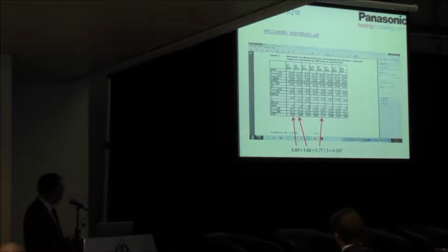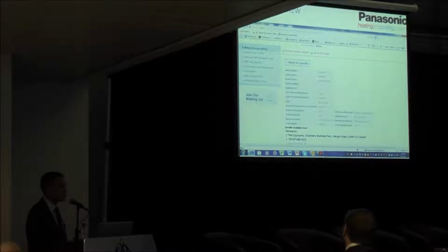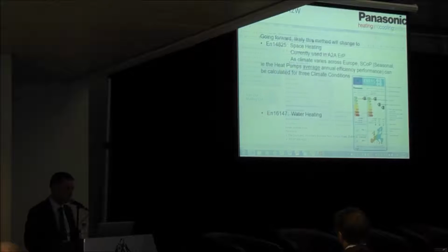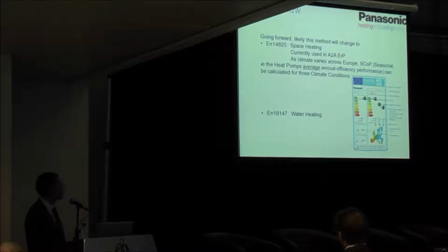But when we look at the three conditions that we have to test it to for HARP, which are air at 7, water at 35, air at 2, water at 35, and air at 7, water at 45, we get an average figure of 4.107. So that's the figure that the BER assessor then uses, and that's what he sees on the HARP database. It gives the information about the unit, when it was manufactured, the SPF, the seasonal performance factor, and then contact details for the manufacturer. Now going forward, those test criteria will change. EN 14511 will change. There'll be two test criteria, EN 14825 for space heating and EN 16147 for water heating. They will probably come into effect from late 2015, 2016.